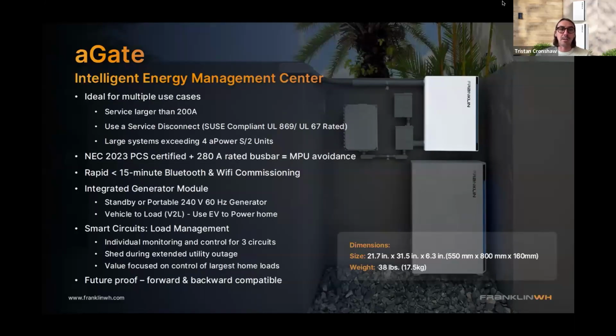Great question. We're getting a lot more than you would think of these 600, 800 amp services across the nation, so it's an important topic. And that really comes to why the A-Gate is being used. If you can use the meter collar, it's a great way to save costs. But in use cases where you have larger than 200 amp services, as just mentioned, or the meter is detached from the internal service panel, or if you need more than 4 batteries, the A-Gate is still going to be the best desired means of integration for the aPower S or aPower 2.